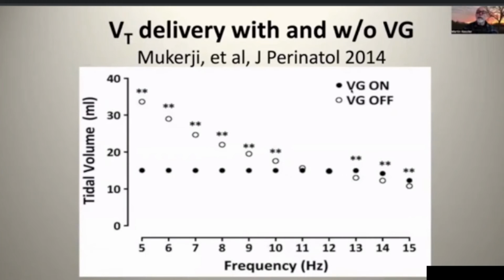Well, with volume guarantee turned on in this study, you can see that something very different occurs. Now the tidal volume stays the same until very high frequencies are reached, and there may be a little bit of tailing off at these really high ones. This was at maximum amplitude. These are really high tidal volumes for high frequency. Typically, we're using around 2. But this just illustrates the point, right? So very different.